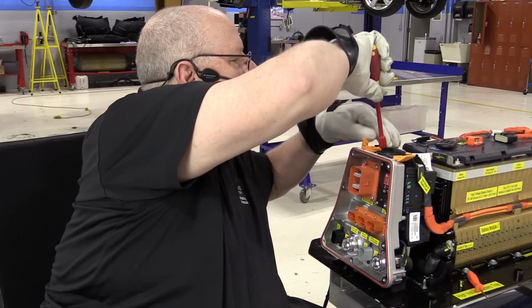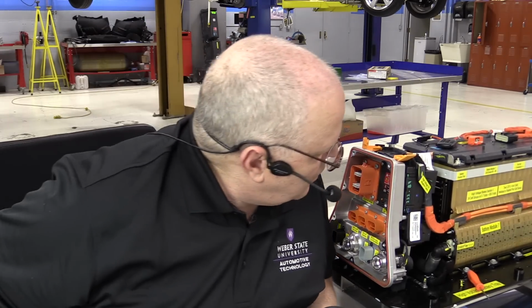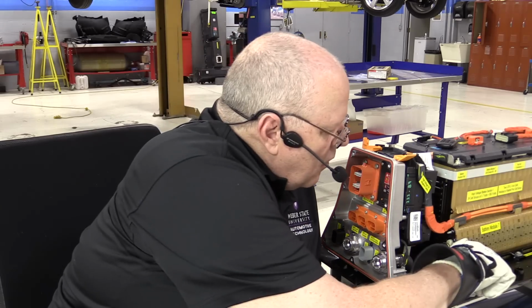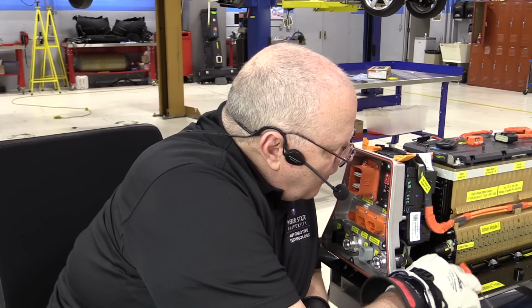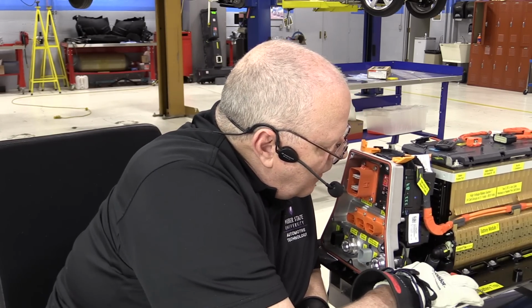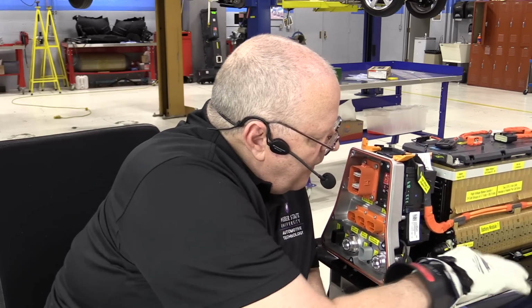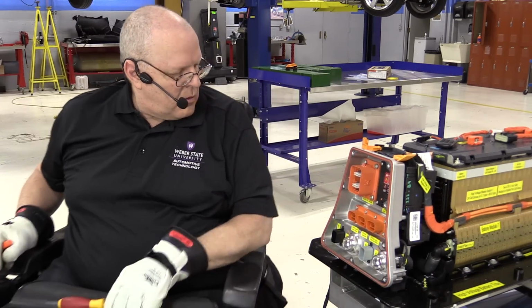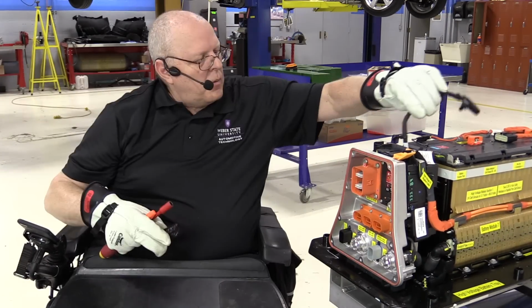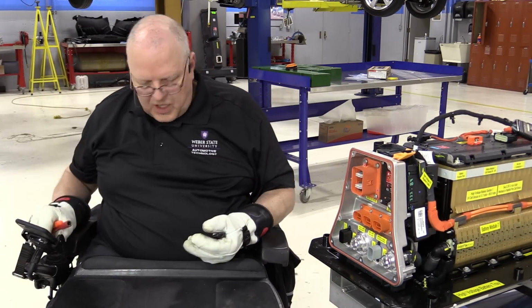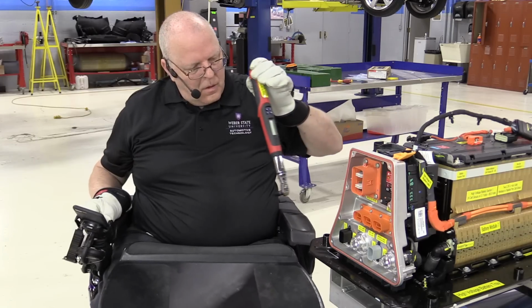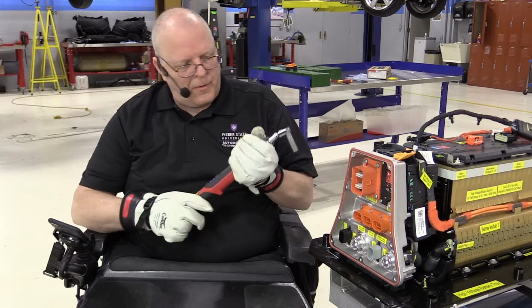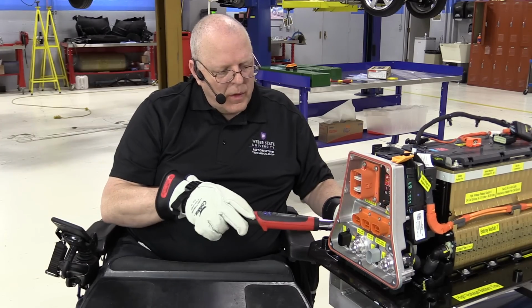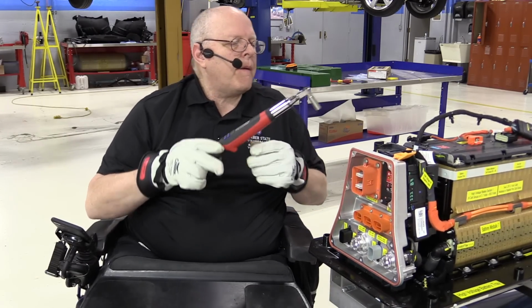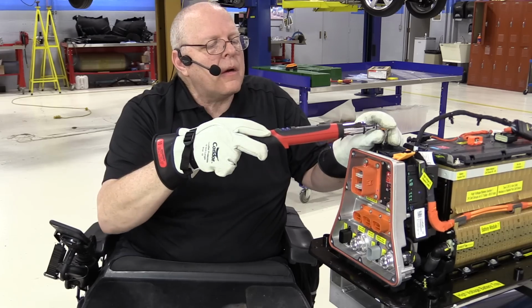Get the nut back on, and of course we'll double torque those to 80 inch-pounds. We'll put the nut down here on the ground stud for one of those 2 ground wires. Get it torqued to 80. And then there's a nut on the other side as well. And then we have our low voltage cable that will come up. So let's get these torqued first. 80.9, 80.7. And then the positive terminal up here.